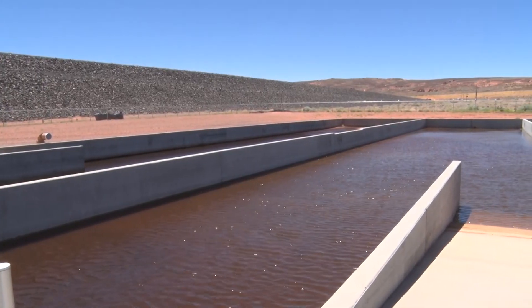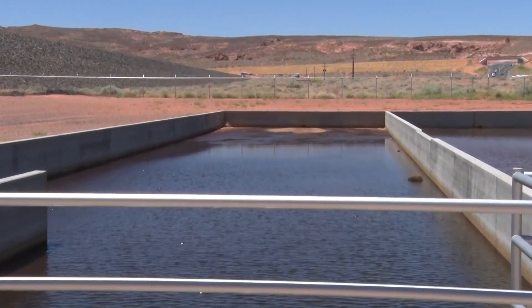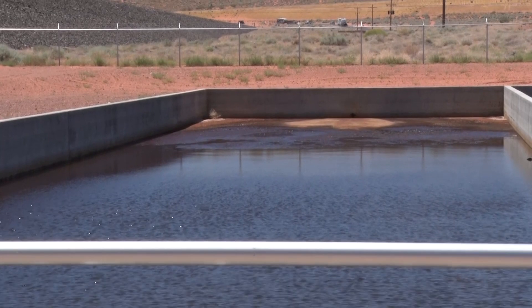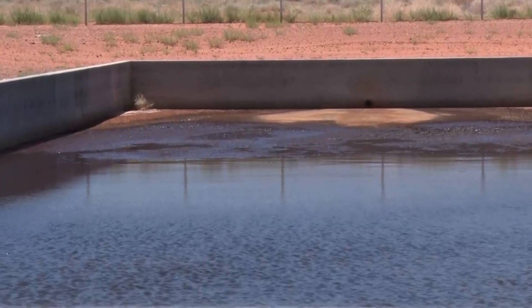Eventually, the captured solids are flushed out into ponds or reclamation areas. When the sludge builds up to a couple of feet thick, it's dried out and removed with a loader and hauled off to the landfill — just normal waste, with no hazardous designations. The material includes iron from the ferric chloride, manganese, arsenic, and sand that blows in.